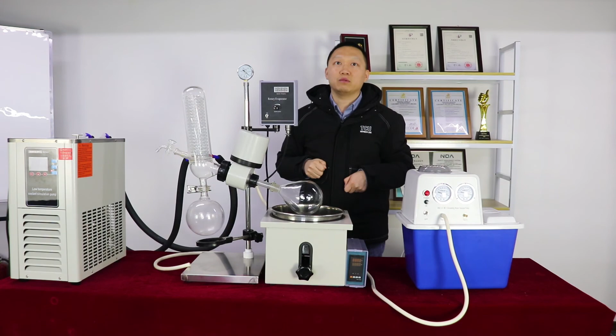It will suck back the water to the condenser. So always make sure to release the negative pressure first, then stop the vacuum pump.